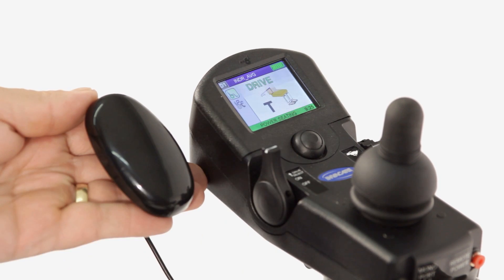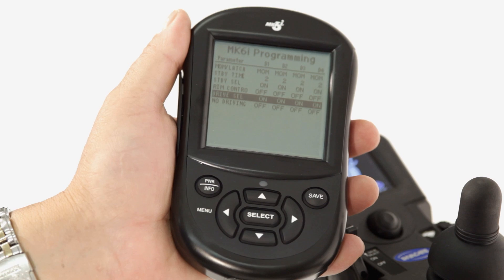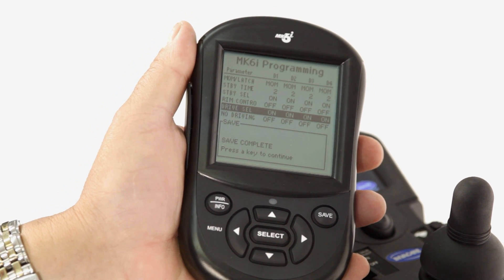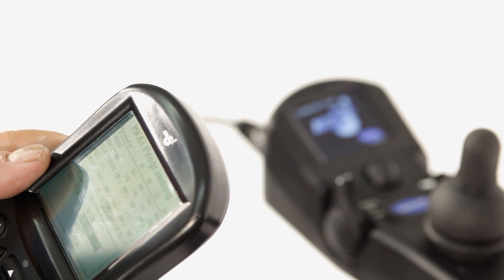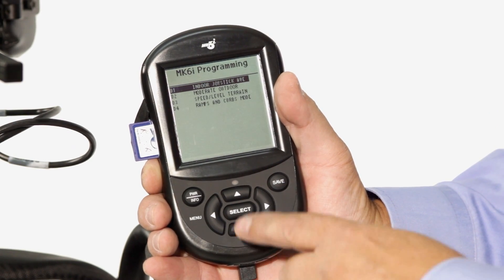Integrated or added external switches make it easy to switch functions. The system can even easily be set up for users without access to switches to change profiles or modes. Use of the handheld programmer makes it easy to dial in performance for individual needs by adjusting accelerations, torque, power, directional speeds, or set up one of several latched driving profiles.